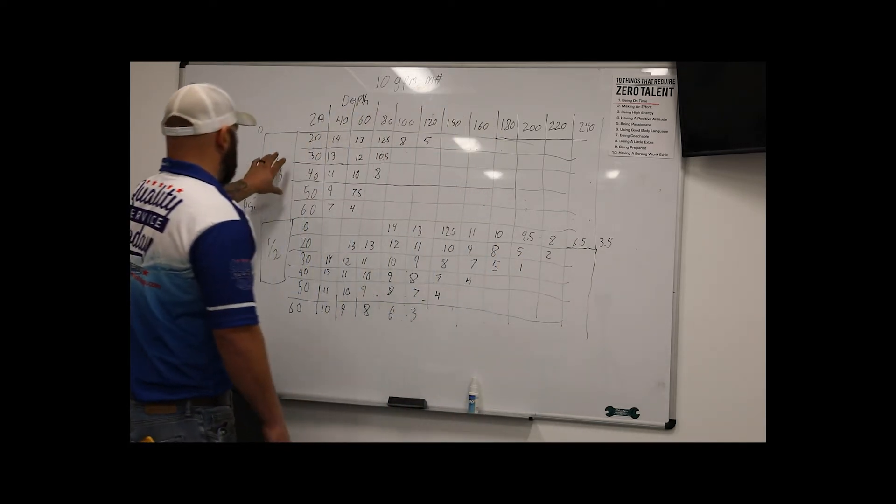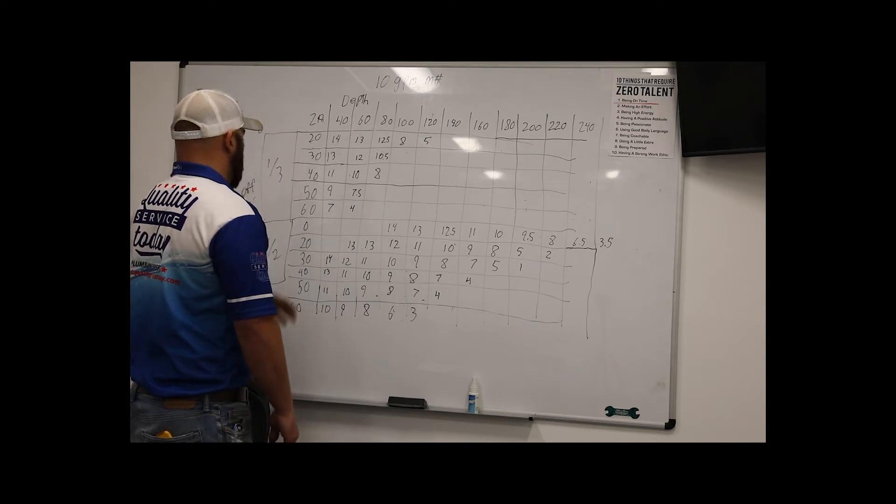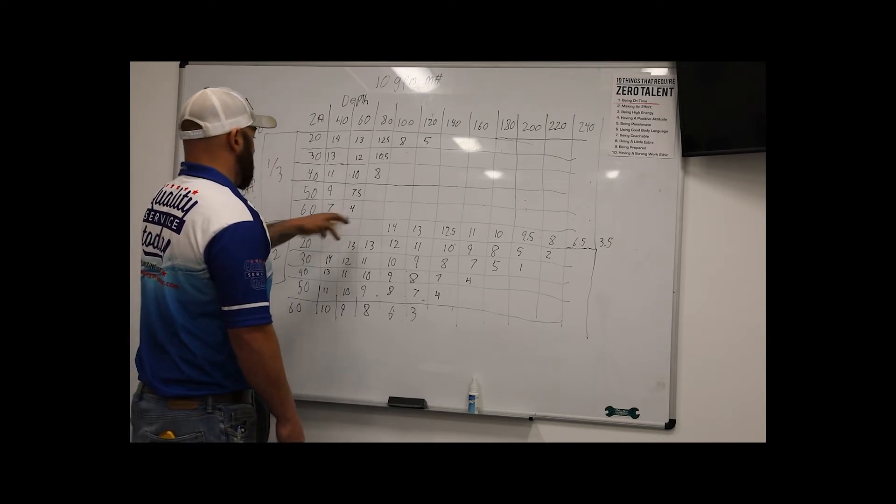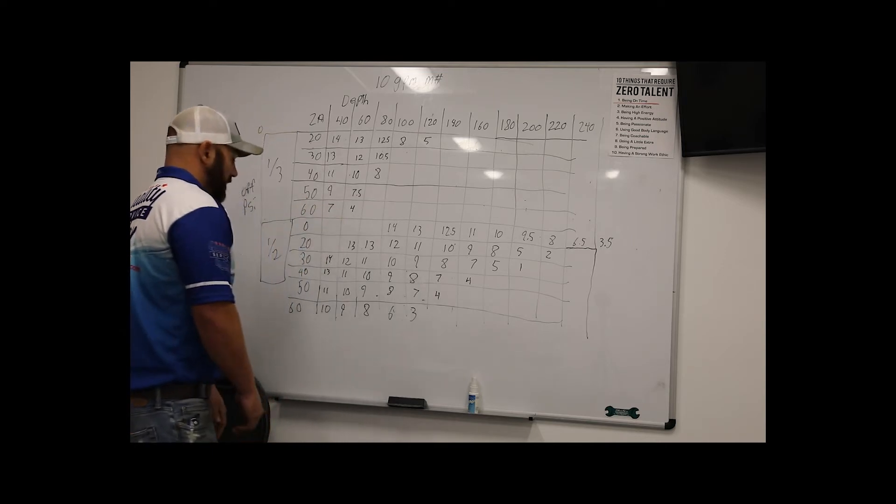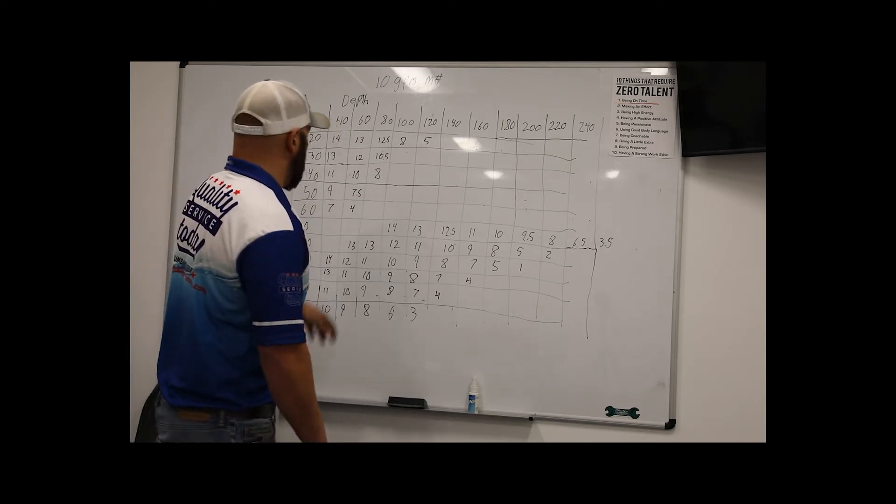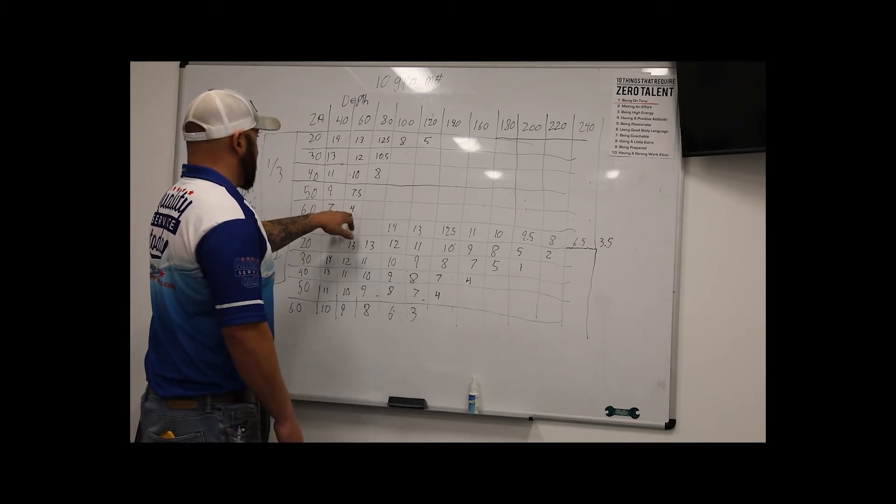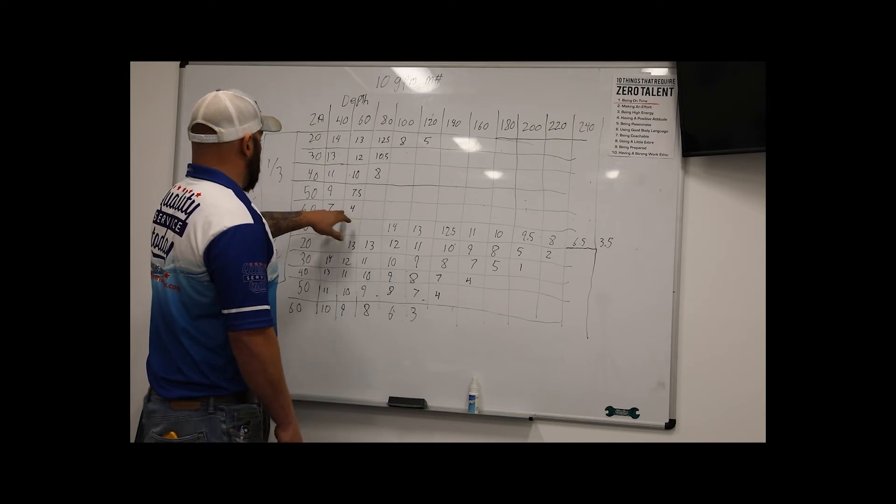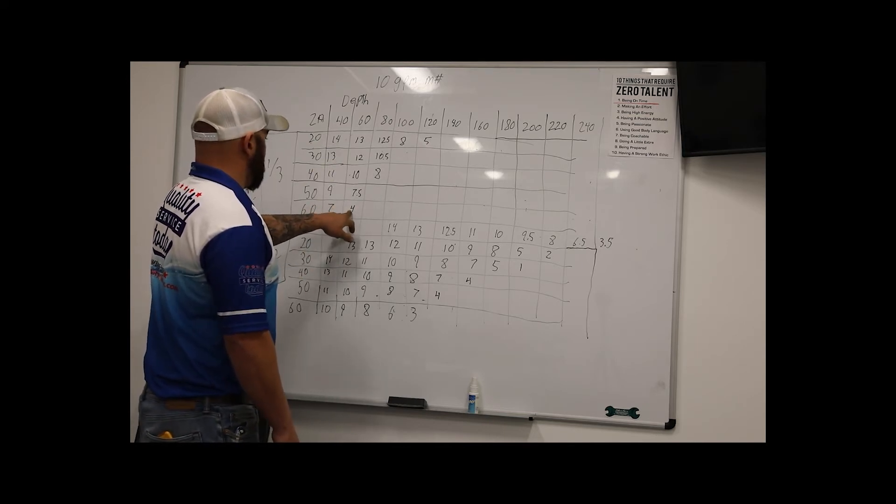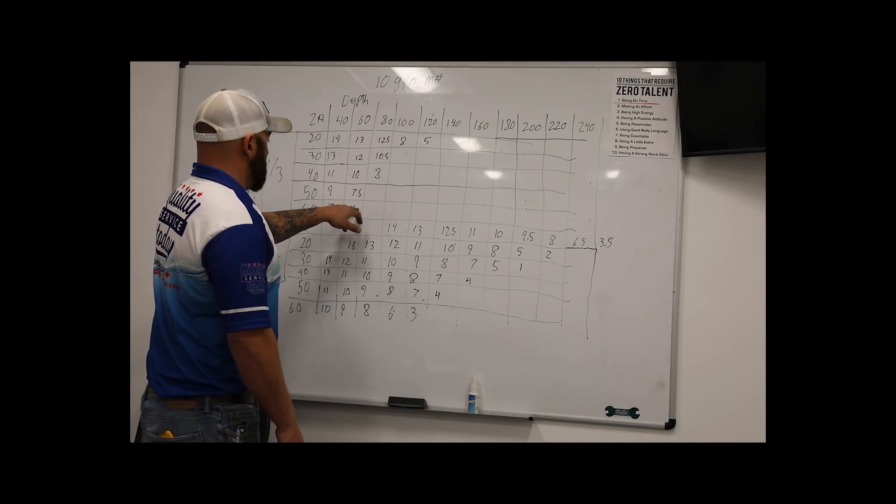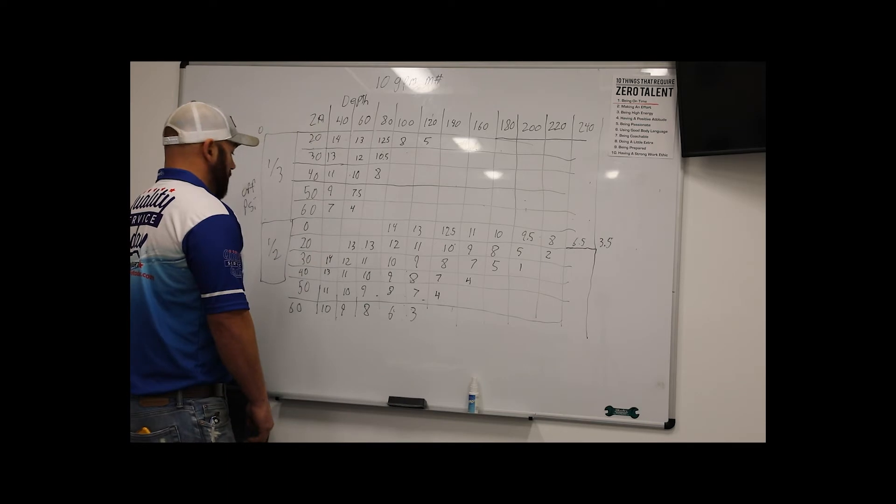So, for instance, the third horsepower, 10 gallon a minute pump, at 60 PSI, you can only hang it 60 foot deep, 4 gallons a minute. That's where I was talking about in the other video, if you have a low gallon a minute well, if you size the pump properly, if you have a 4 gallon a minute well, and you size the pump at your off pressure and your depth, you're never going to over pump that well because it can only move as much water as what's coming into it.